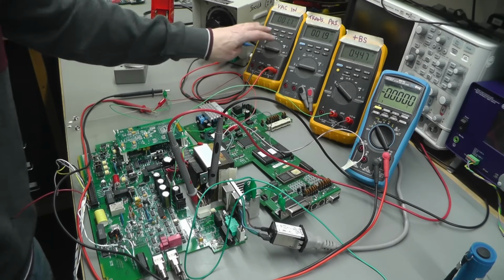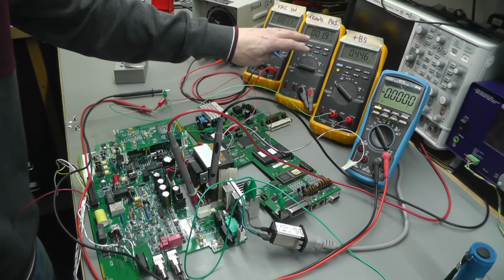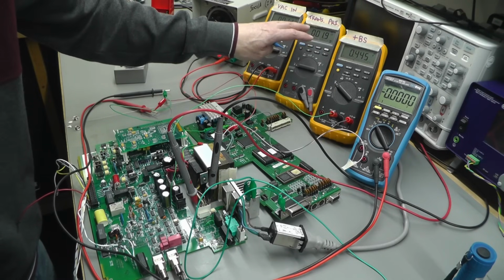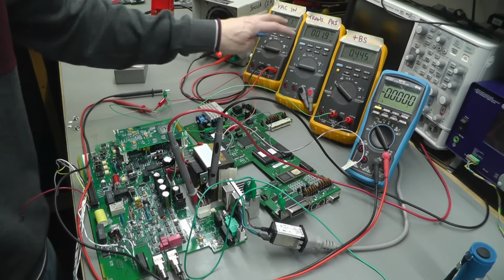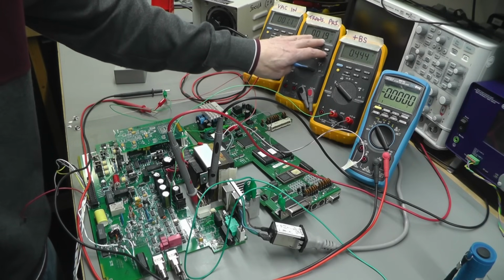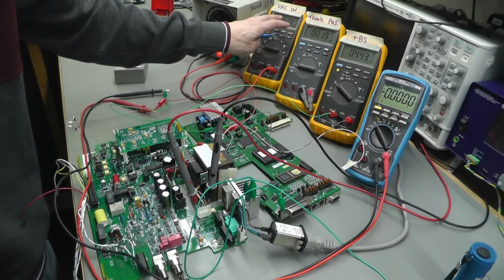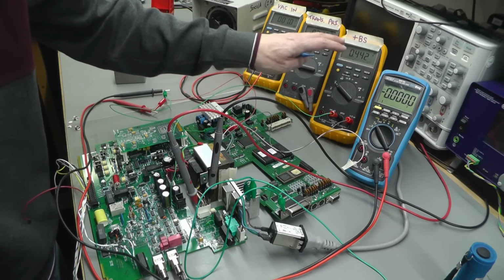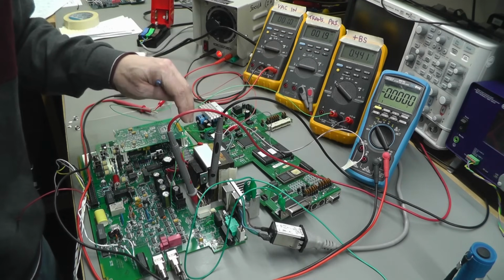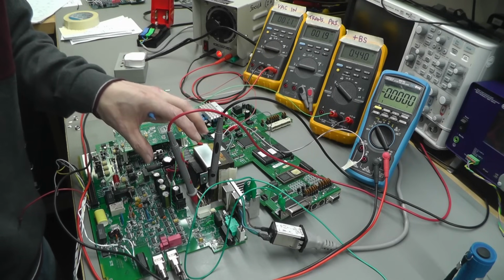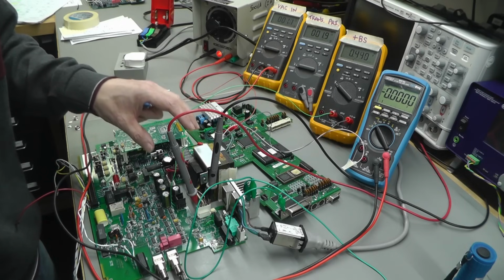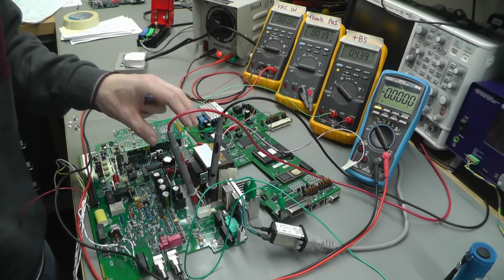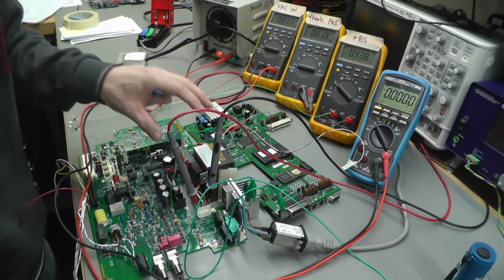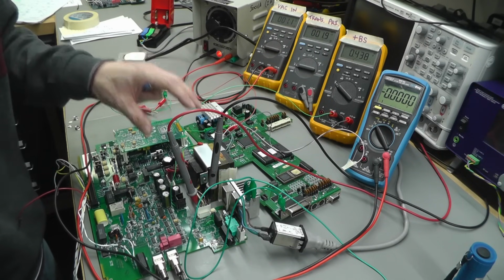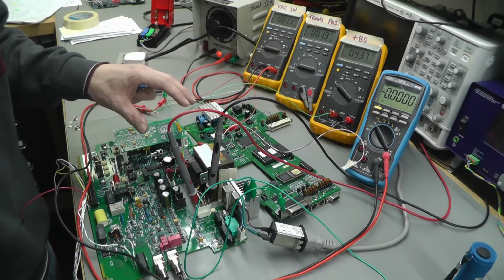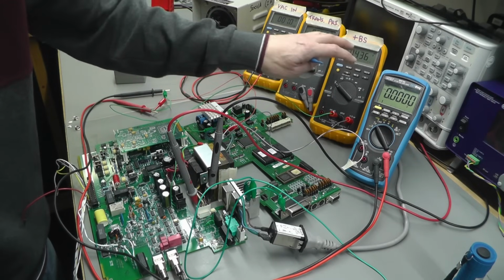So multimeters at the back. I've got the AC input coming from a variable transformer, and the AC voltage across the transformer primary so that I can see what's going on. If the pre-regulator's working, I should see this voltage being slightly less than the AC input. I'm also measuring a positive VS supply. It's an unregulated DC supply from the secondary on the transformer, going through a little voltage doubler, and the schematic says it should be between 34 and 38 volts. I've never tested it previously because I've never hooked up that secondary, so I thought it was worth monitoring.